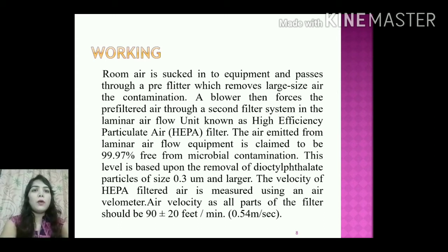Working of laminar airflow cabinets. Room air is sucked into the equipment and passes through a pre-filter, which removes larger air contamination. A blower then forces the pre-filtered air through a second filter system in laminar airflow units known as the high efficiency particulate air filter.